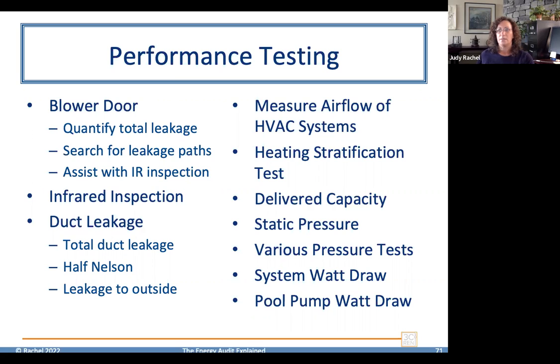Blower door testing, IR inspections with or without the blower door, the 3 main duct leakage tests, measuring the system airflow for both the heating and cooling system and the ventilation that's in the house. So whether that's a balanced ventilation system or, say, bath fans. There's something called the heating stratification test, and the delivered capacity test, figuring out how much capacity of the heating and cooling system is actually being delivered into the home, static pressure on the heating and cooling system itself. There's other pressure testing. You can do zonal pressure testing across doors.